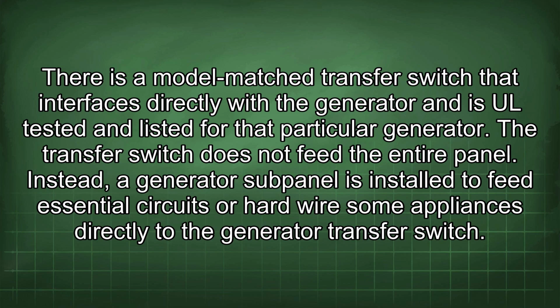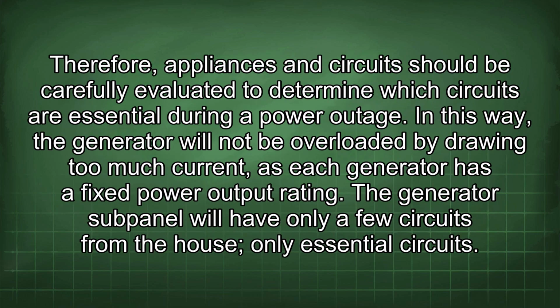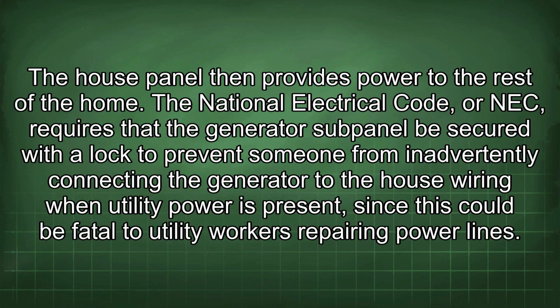Instead, a generator subpanel is installed to feed essential circuits, or hardwire some appliances directly to the generator transfer switch. Therefore, appliances and circuits should be carefully evaluated to determine which circuits are essential during a power outage. In this way, the generator will not be overloaded by drawing too much current, as each generator has a fixed power output rating. The generator subpanel will have only a few circuits from the house, only essential circuits. The house panel then provides power to the rest of the home.